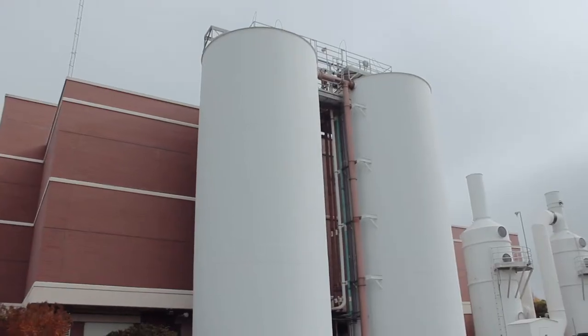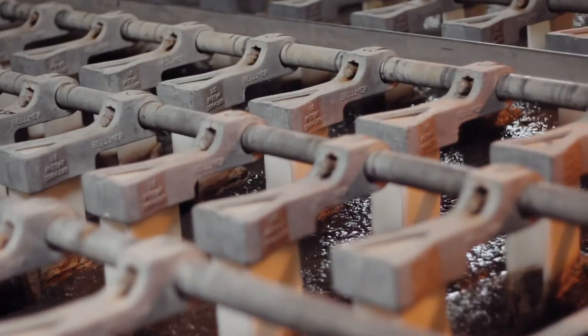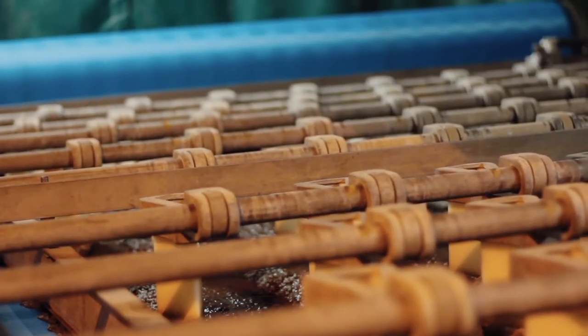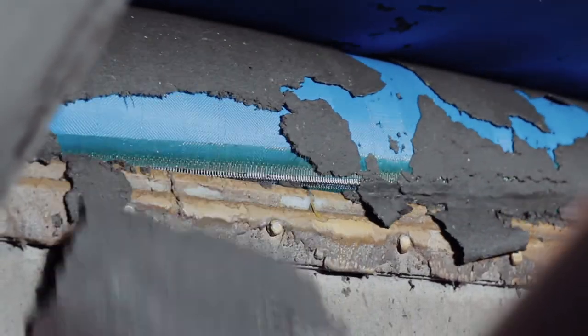Remember back at the beginning of the process where we separated the liquids from the solids? When the solids come, we pump them to the blend tanks outside the solids building. In that blend tank, it is dosed with lime. Once we're ready to dewater the press, we pump the solids into the solids building and do a final dose of lime. We let it sit for two hours. From there, we pump it to our belt press, where we add polymer, which clumps it together and removes the excess liquids from the sludge to make the sludge dryer — a cake product that we produce.